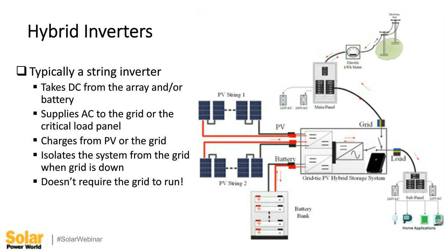When you start a motor up, it takes more power to get started, so your hybrid inverter needs to handle that. And then, of course, it doesn't need the grid to run. So if the grid drops down, your house still goes. It should be able to draw power from the PV array to supplement the batteries. If there's no PV, nighttime, it draws completely from the batteries. As the PV comes up, it determines what it needs, charges if it's available, supplies power if it's needed.